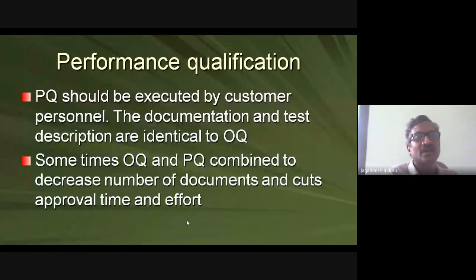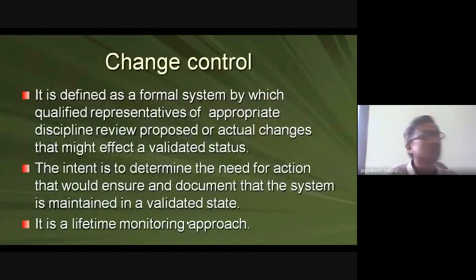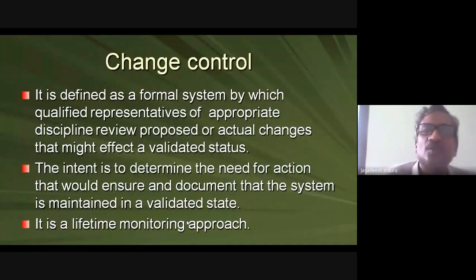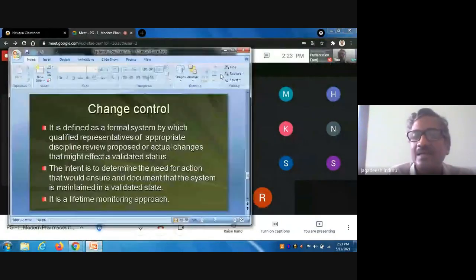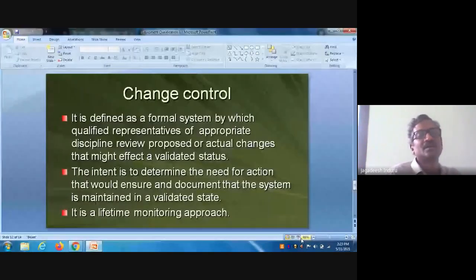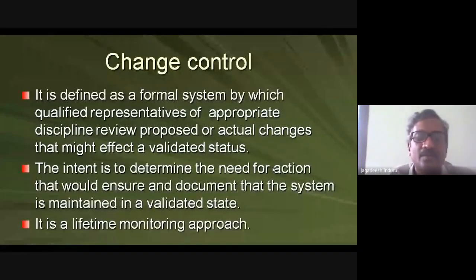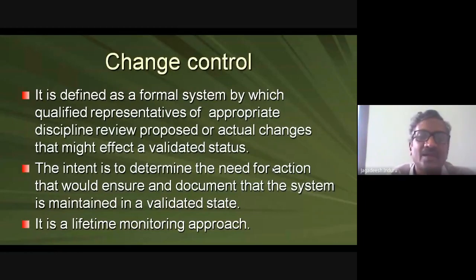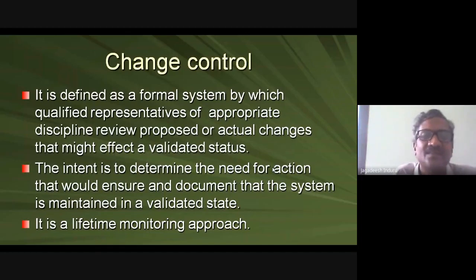After PQ, create a logbook for the equipment to record all work performed. You need a Change Control Program: draw an SOP — Standard Operating Procedure — so that everyone operates the equipment in the prescribed manner only. For example, when operating a projector system, you must switch on main power first, then the subsystem, then attach to the projector — this fixed sequence is what the SOP captures. The repeated steps done regularly must be written in the operating procedure.